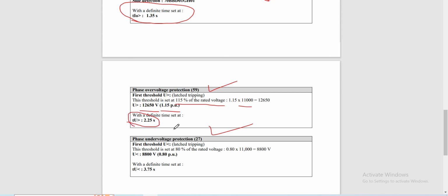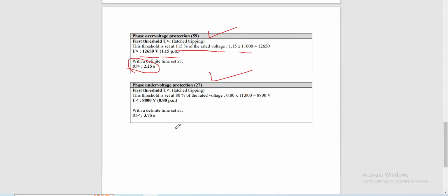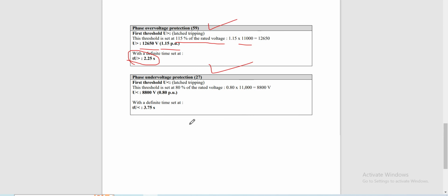2.25 seconds. Last, our phase undervoltage protection is set at 80% of the rated voltage, which is 11 kV multiplied by 0.80.